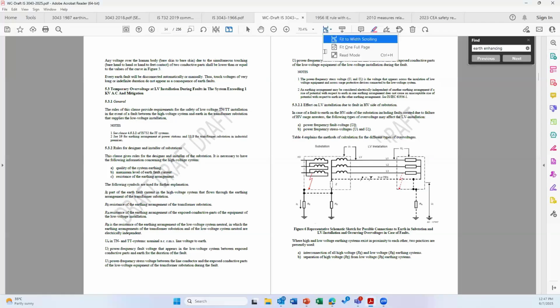Sir, this is clearly addressed. There is a potential being transferred for the fault on the HV side. That is getting transferred to the LV side, to the LV installation, and impresses a stress voltage on the equipment and a touch voltage on the personnel. There are clear guidelines issued for this specific subject. This is a transfer potential that can affect, so how to mitigate it? Here also equipotential bonding plays the role. The earth electrode resistance can be addressed in the HV substation where you have a lot of yard area. You can do a lot of things.